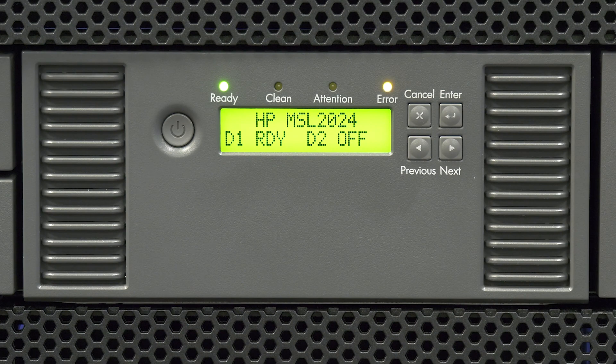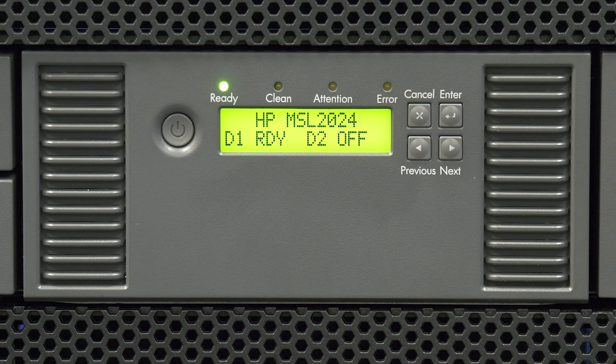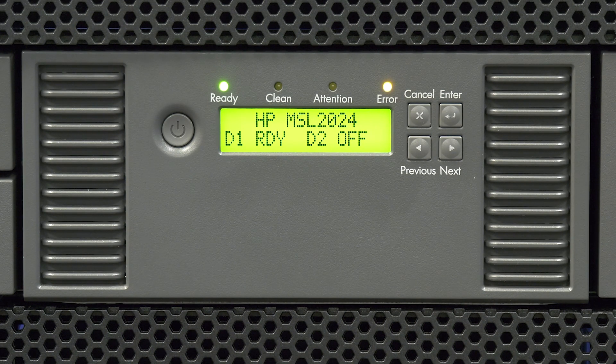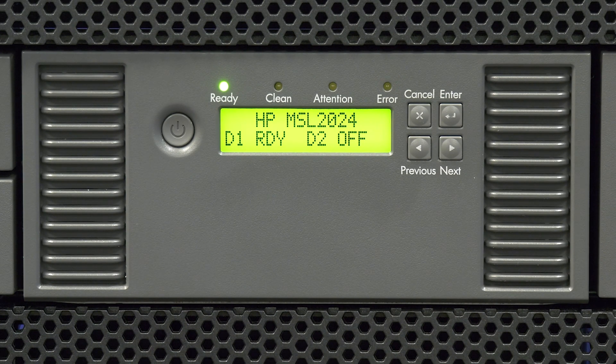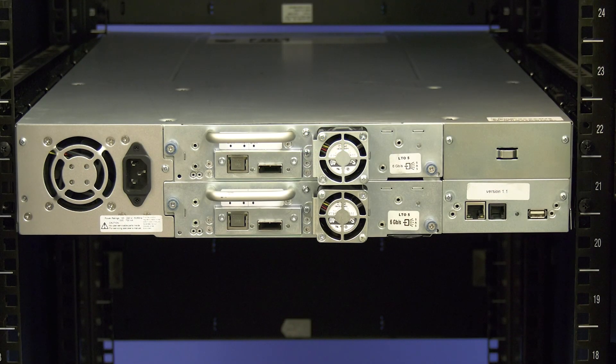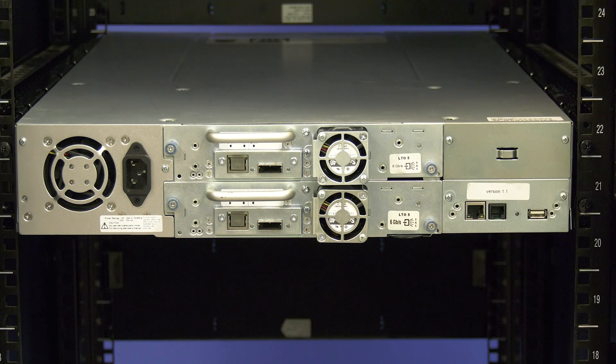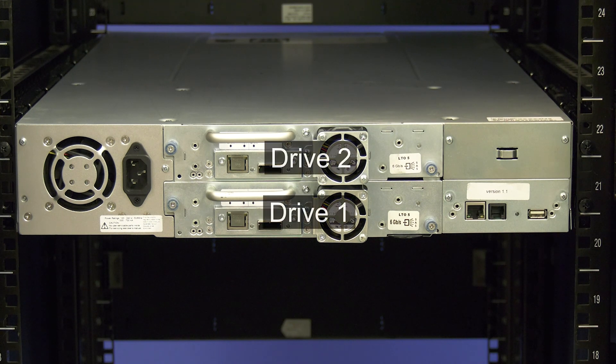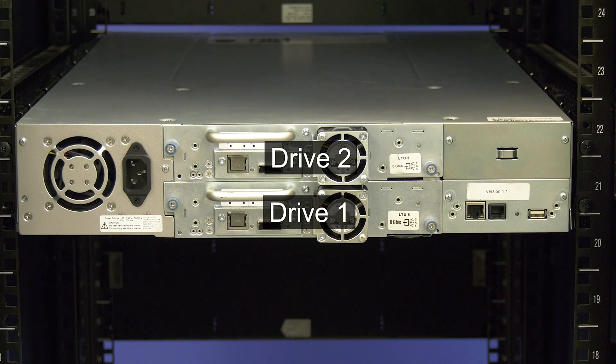On the front panel you will see the drive status displayed beneath the library name. If a drive has an error you will see it displayed here. Please note the drives in this library are numbered from the bottom up when looking at the library from the rear. This means drive 1 is the bottom most drive and they are numbered consecutively up from there.